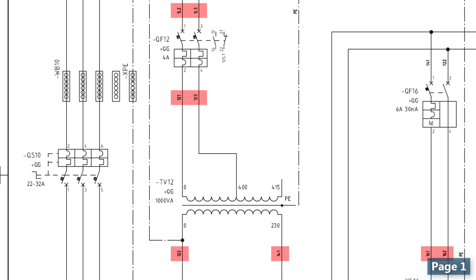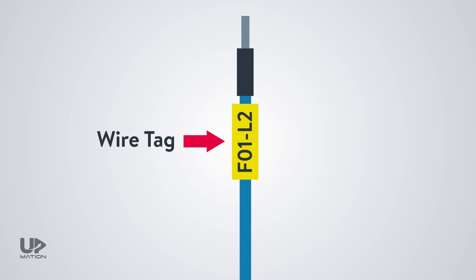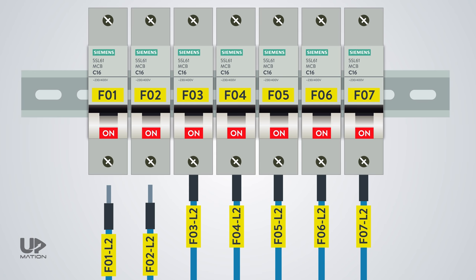One of the branches goes into a two-pole circuit breaker and from there powers a transformer. If you have noticed, there are some numbers on the wires. These are called wire tags. Wire tags are very helpful in case of troubleshooting. So that, when a wire gets out of its connection point, you can easily look at the wiring diagram and figure out where it should be connected again.